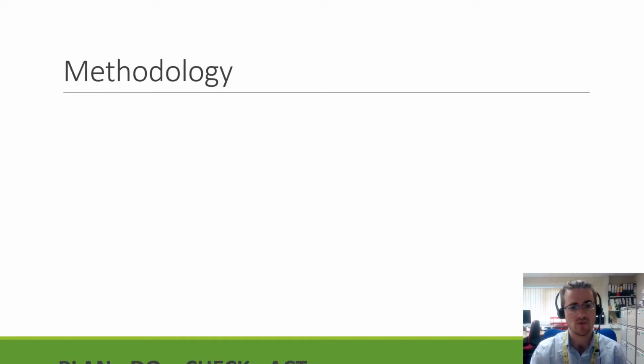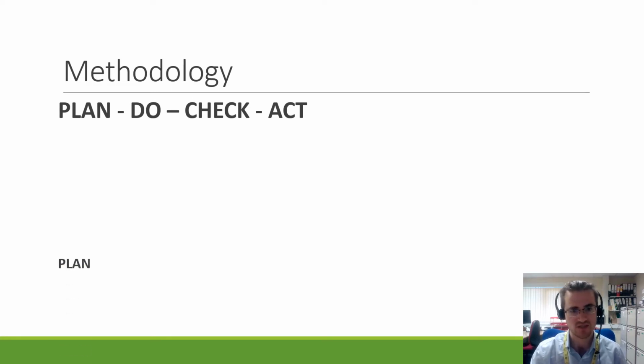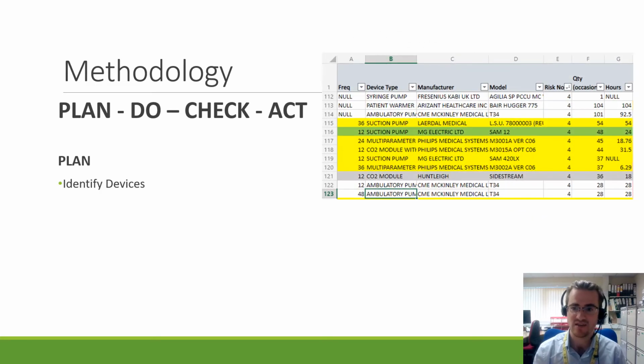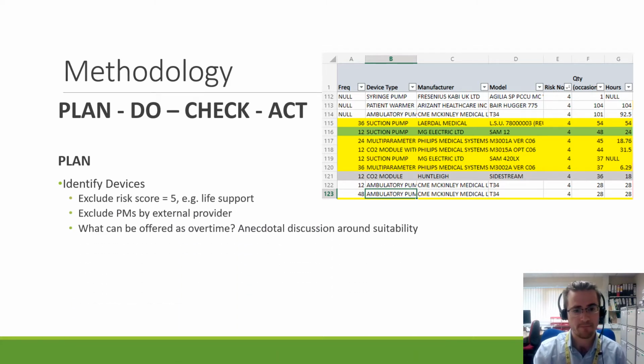How we went about doing this, we applied the Plan, Do, Check, Act cycle to our risk assessments. For the plan stage, we identified devices using our valuable source of information, our asset management database, where we collated information such as the quantity of PMs, and also based on previous work we were able to get a cumulative amount of hours that group of PMs represents. We would exclude anything that was life support or anecdotally just wasn't going to be viable, so small quantities of assets, as a trade-off for the amount of time and effort that the risk assessment was going to require. And then also we looked at potential overtime opportunities as another recommendation from the guidance document.